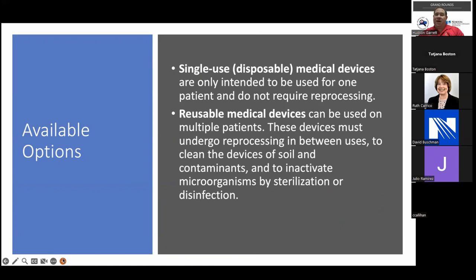I would encourage you strongly, if you do this, to make sure those single-use devices are sterile. Do not accept something single-use that is not sterile, unless it's a non-critical device, which is a bit different, like a blood pressure cuff. We still have reusable medical devices, which are inherently risky because of the reprocessing process, the equipment, storage and handling.